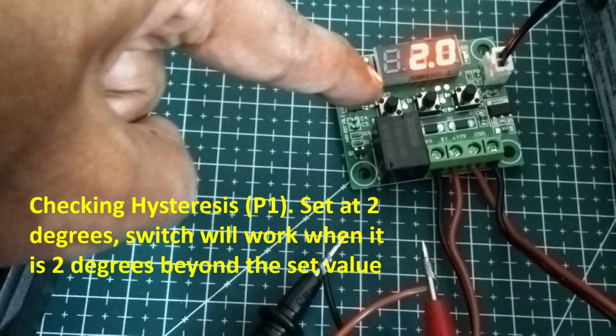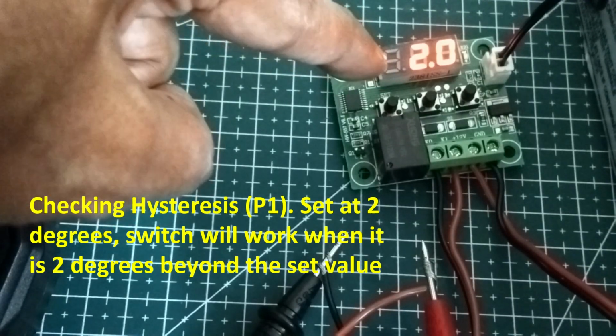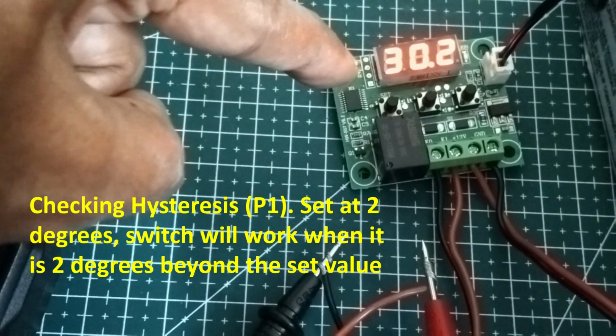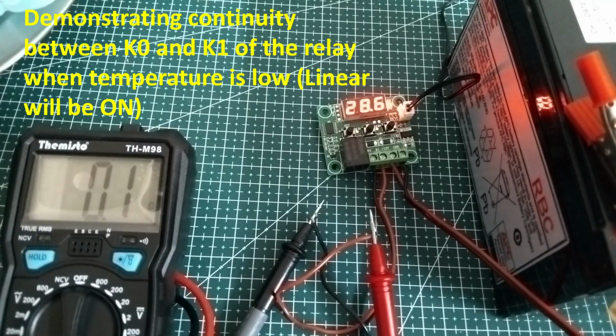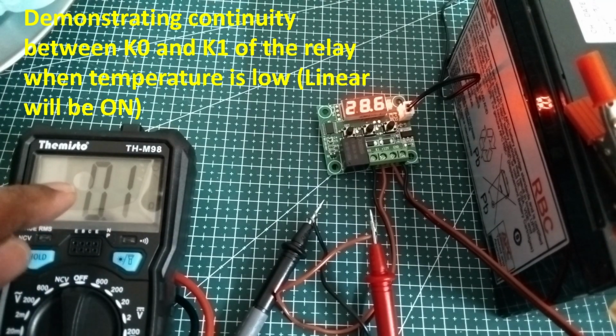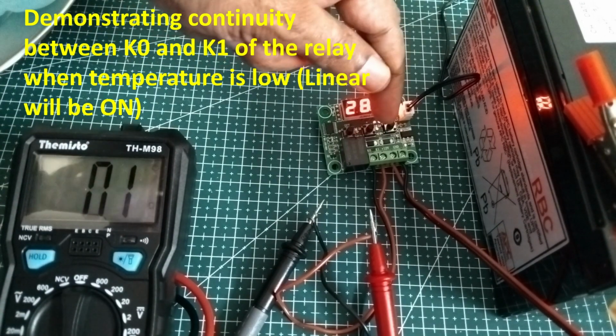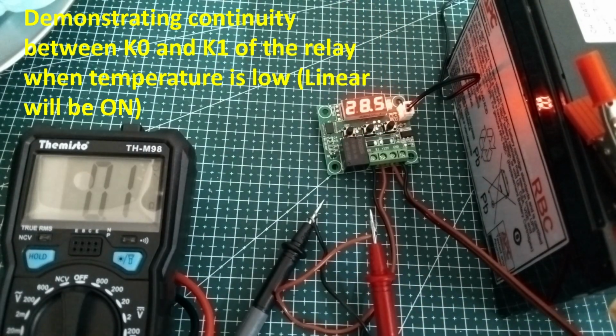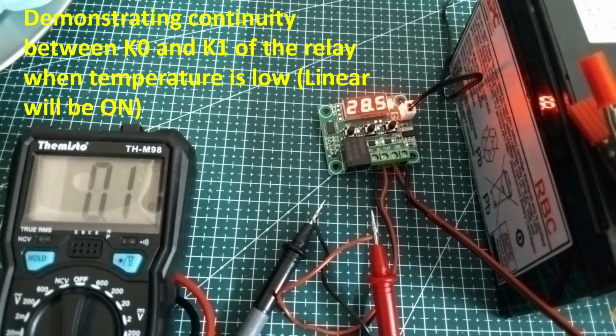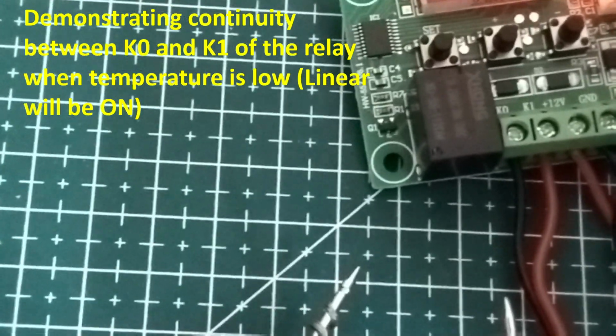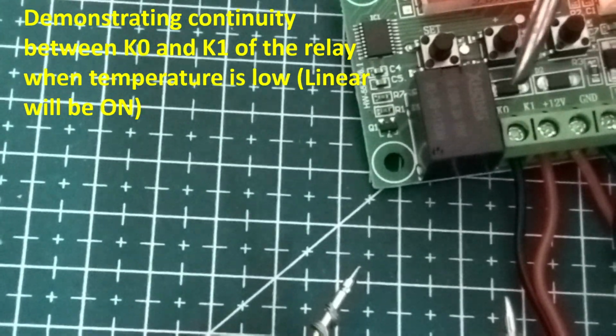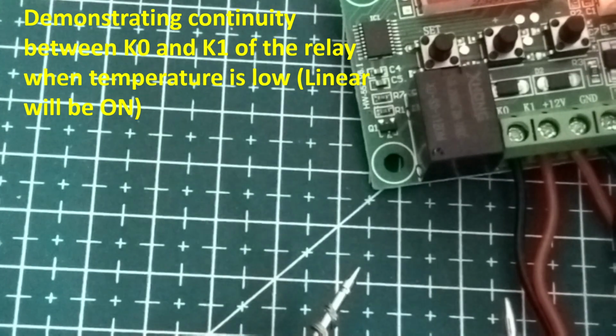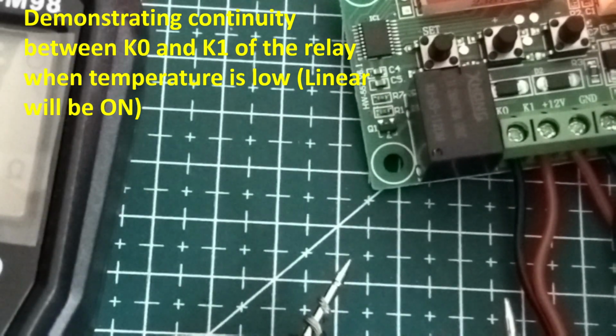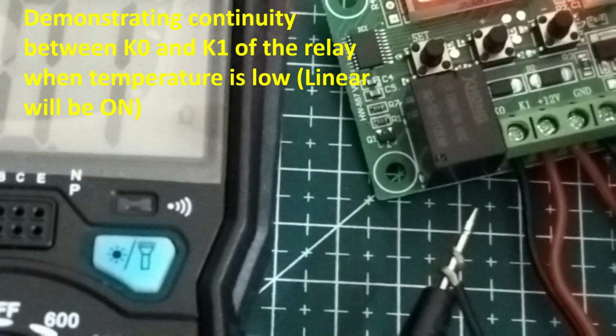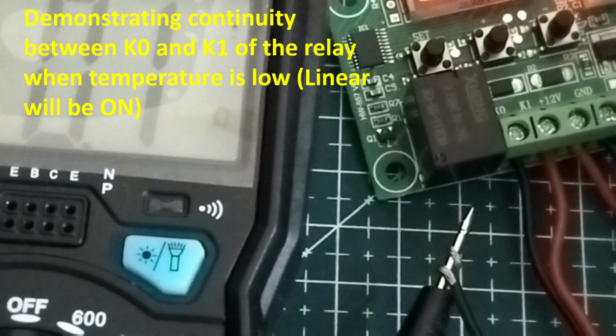The hysteresis is set at 2 degrees centigrade, meaning the switch will activate when the temperature is 2 degrees beyond the cutoff. You can see that now it's connected, between K0 and K1. I'll enlarge and show - this is K1 and K0. So the switch is on when the temperature is 28.3.